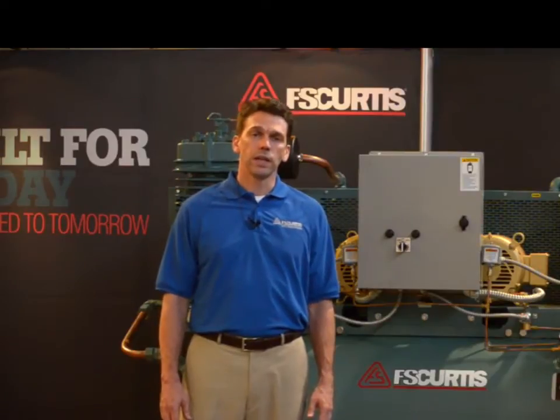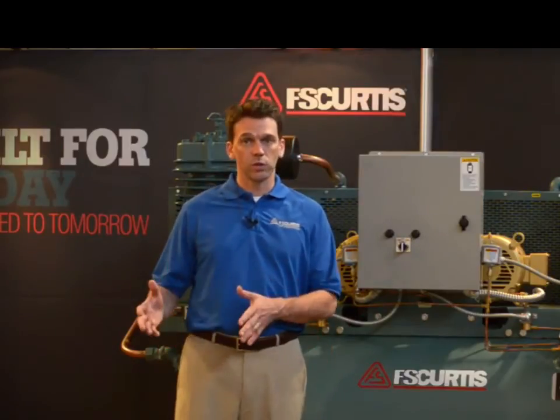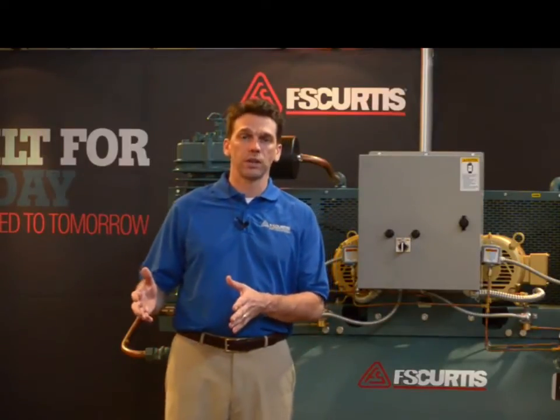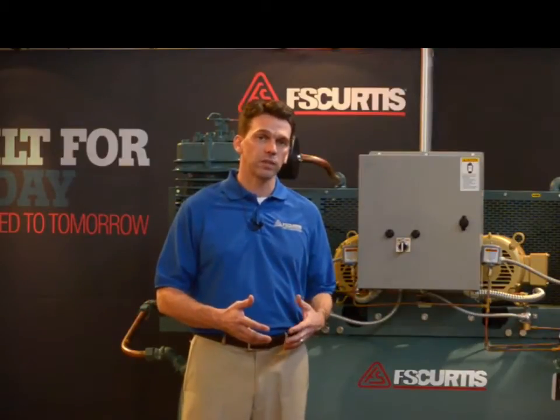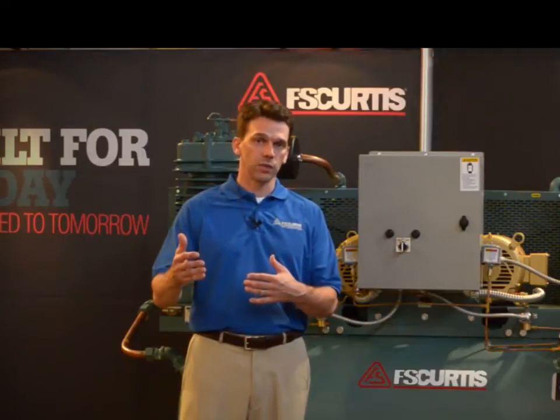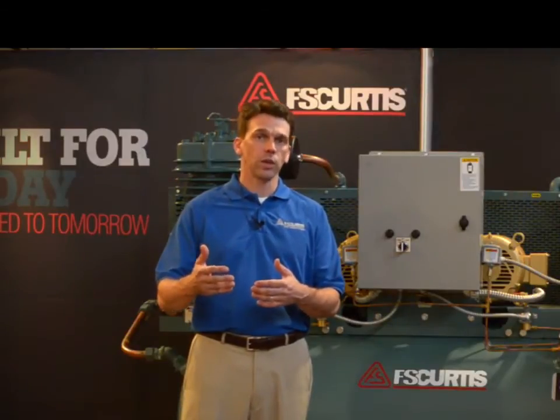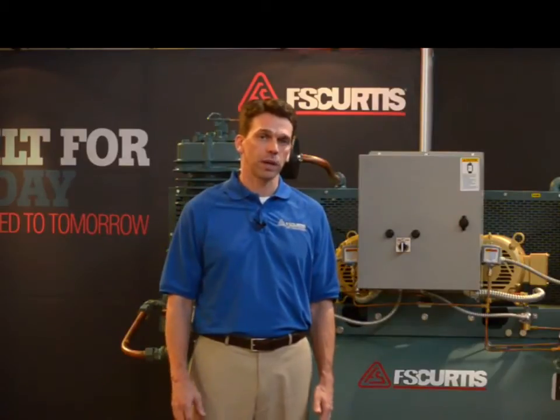They also have very high temperatures at discharge unless you use an after cooler. And finally, even though a lot of reciprocating compressors advertise 100% continuous duty cycle, the typical rule of thumb is that if you're going to run it for 45 minutes, you should let it rest for 15 minutes — a 75-25 duty cycle — in order to ensure optimal pump life.